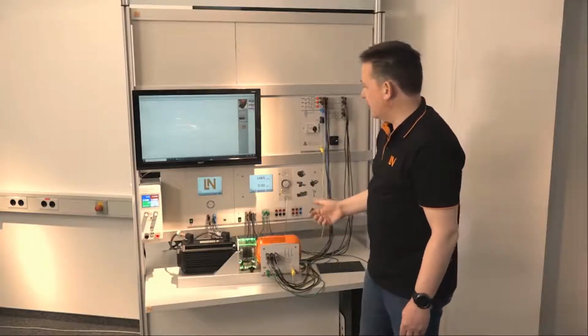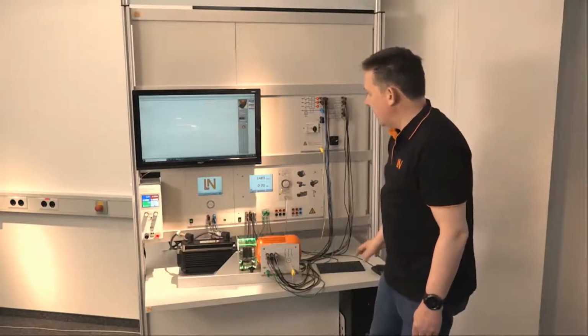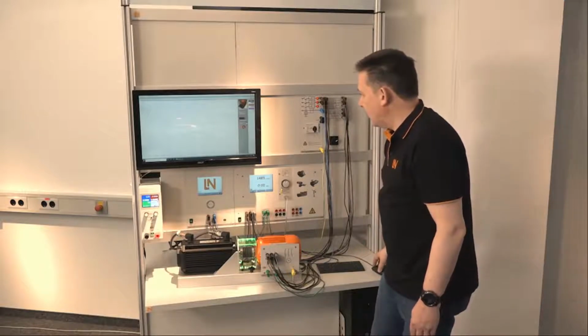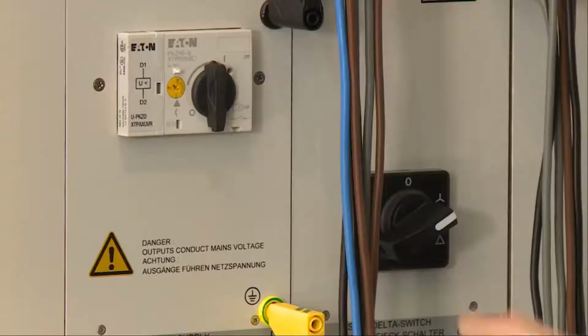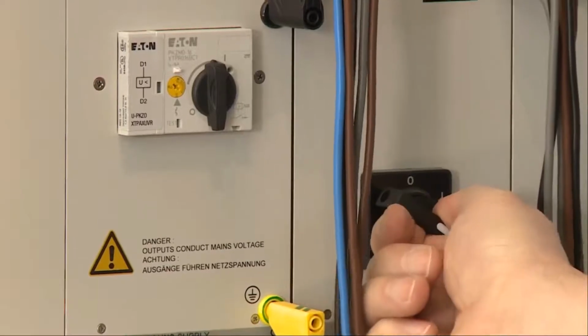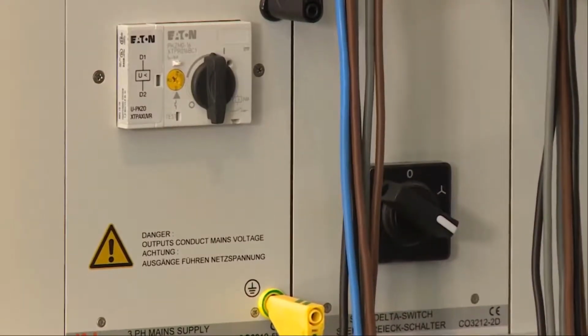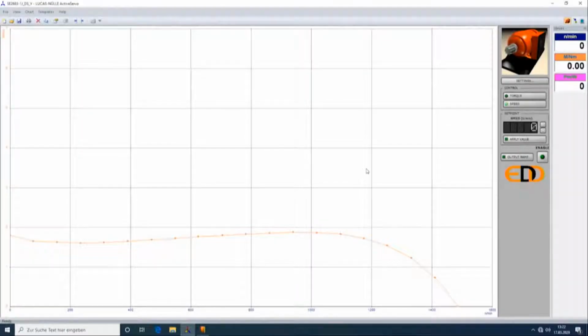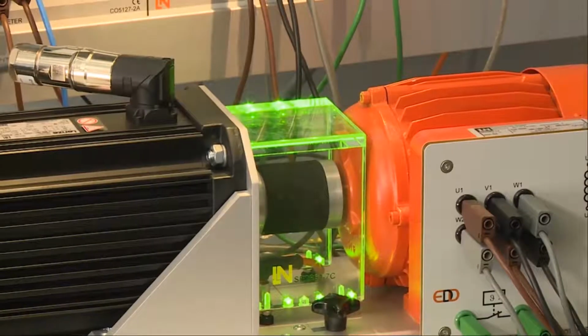for the star circuit. The next step is, I will press the enable button again, and now we switch the motor to delta connection, and then we will see how the motor behaves in delta connection. I will press the enable button again, start the system pressing the 1 button, going to output ramp, and then the system records the characteristic for the delta.